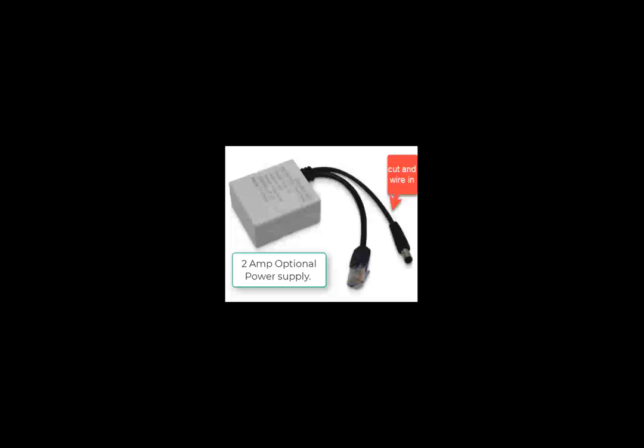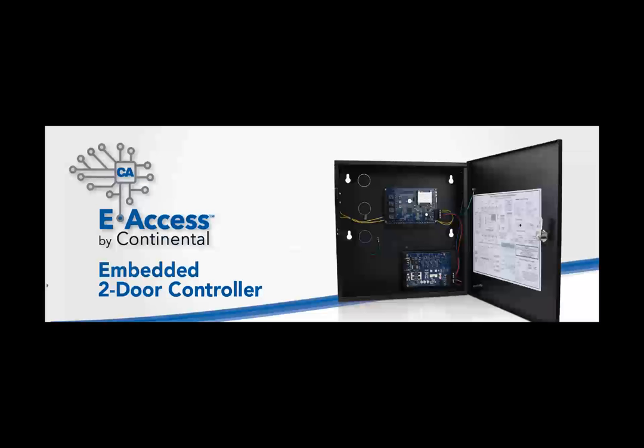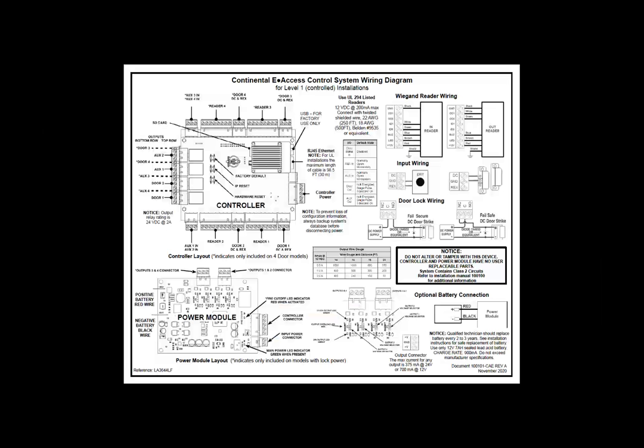The eAccess embedded 2-door controller supports 2 doors with 2 readers on each door. In addition, it contains 4 relays, 2 for door locks and 2 for auxiliary relays. It also contains 3 inputs for each door. One for rex, one for door position switch and one auxiliary input. The wiring diagram for the 2- and 4-door controllers are the same wiring diagram with the differences noted with asterisks. The 2-door controller is also available with a power package that includes power for door locks. The power module has additional connectors on it to provide lock power and has connections for a backup battery.